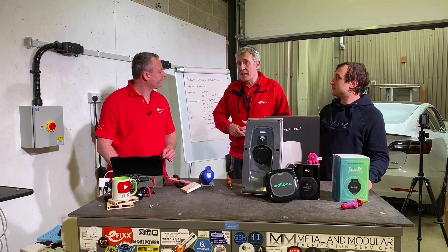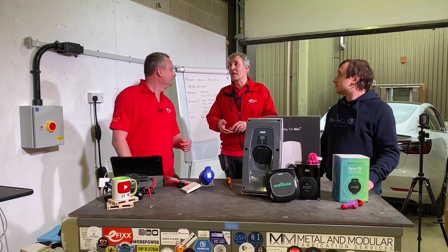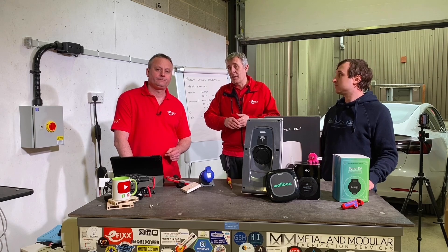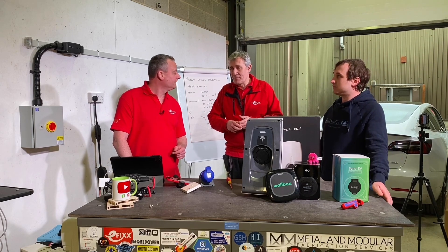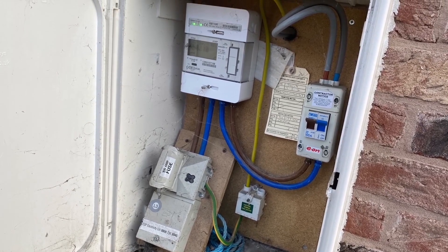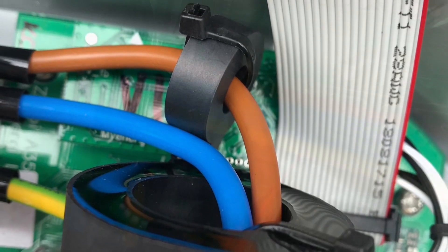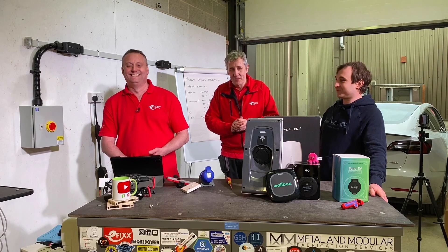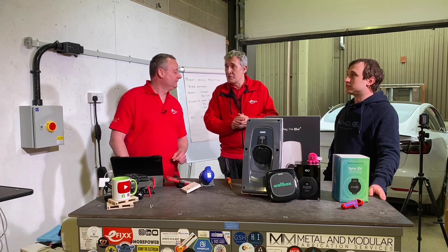There are other things to think about if you have a lot of electric appliances - an induction hob, electric shower, storage heaters - combined with a 7 kilowatt EV supply, that can add up to a massive load and risk blowing the incoming supply fuse. EV chargers have thought about this: you can get features that will automatically reduce the load going to your car momentarily when other high-demand appliances kick in, preventing that incoming fuse from blowing.